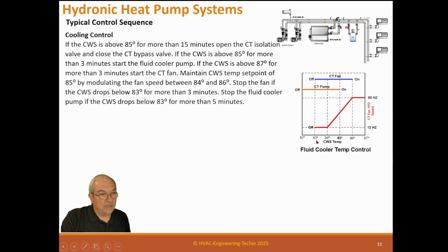Remember that VFDs have this minimum speed because the fan that cools the windings is on the shaft of the motor. So you can't take the motor to 0 speed because it'll burn the motor, unless you have a true VFD motor, which has a separate motor and cooling fan. I've actually never seen one. I know they make them, but they're really expensive, so no one buys them. So for a motor, you can't take it to 0 speed.